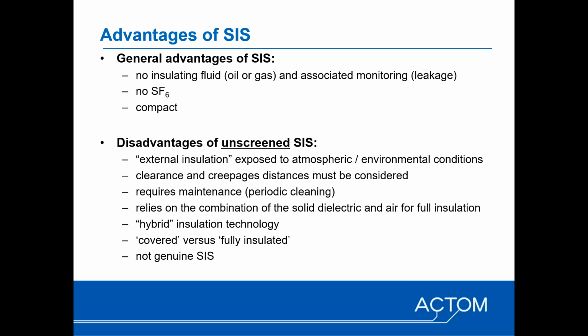Now, some of the disadvantages of unscreened solid dielectric insulated switchgear. Firstly, there's external insulation, which Johan will cover later in his slides, which is insulation exposed to atmospheric and environmental conditions. Therefore, you have to consider creepage as well as clearances. Because they're exposed to the environment, they require periodic cleaning and therefore maintenance. It's not a maintenance-free solution, and that has pretty much been, I would say, the downfall of unscreened solid dielectric switchgear in the past.